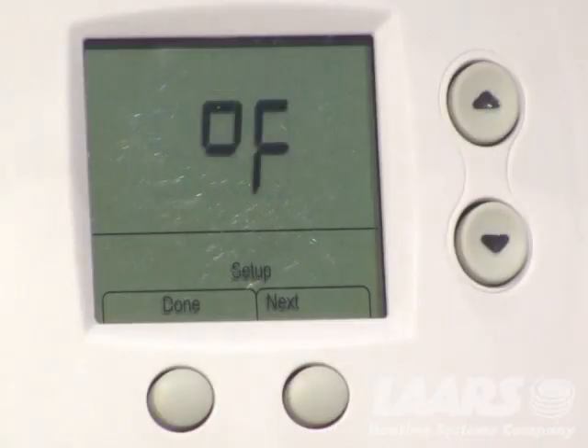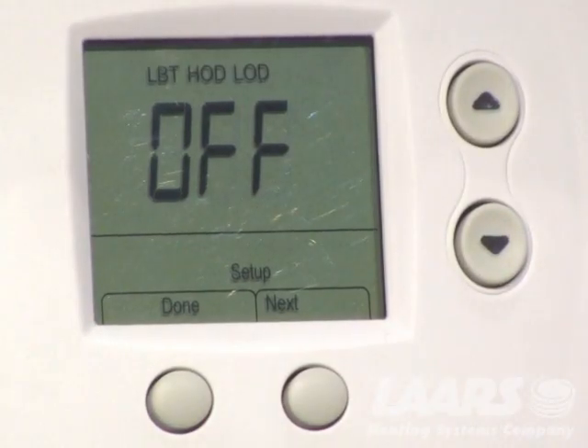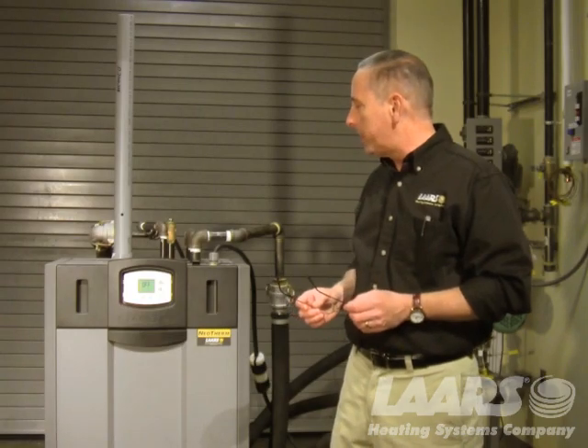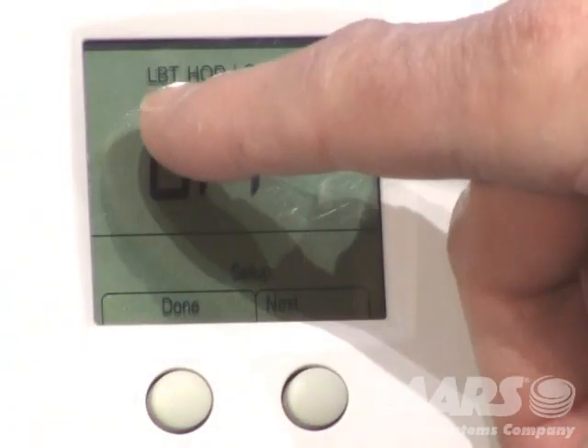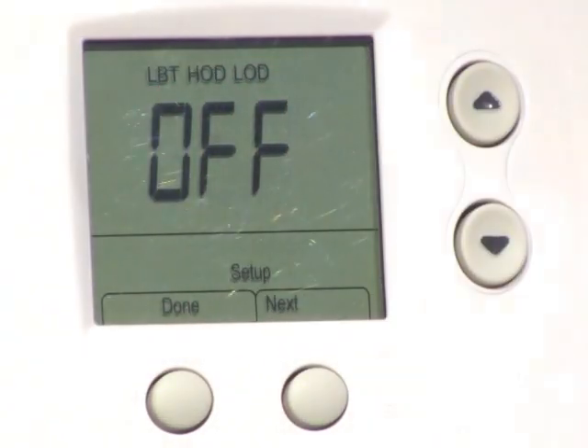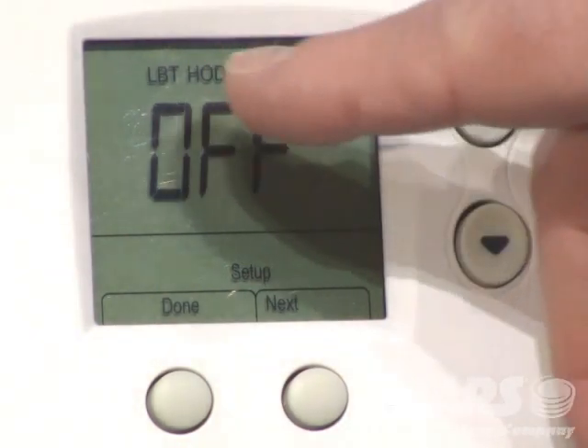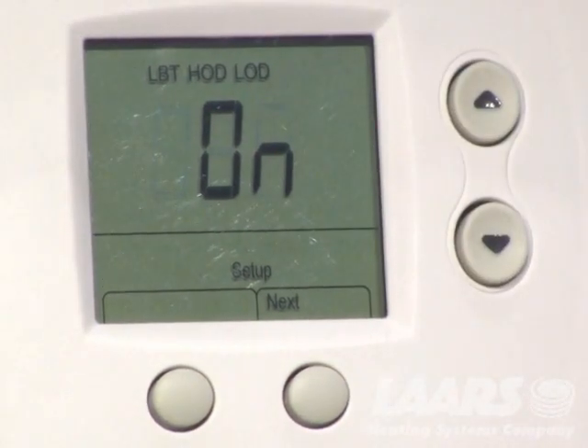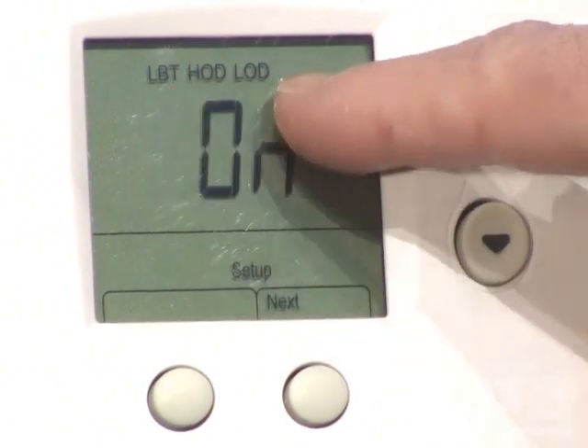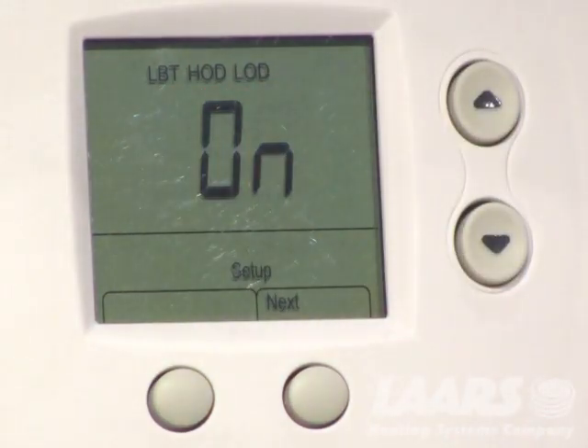From here, use the next button. Press next and this is the screen you use to set up your outdoor reset. Right now it's in the off position, registering LBT, HOD, and LOD. If you turn it on using the up arrow, the next three parameters that appear will be low boiler temperature, high outdoor, and low outdoor — we'll explain those in a moment.